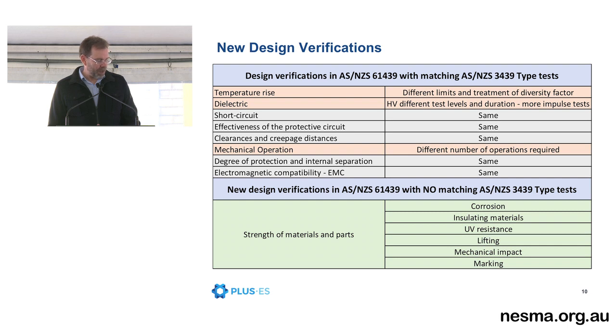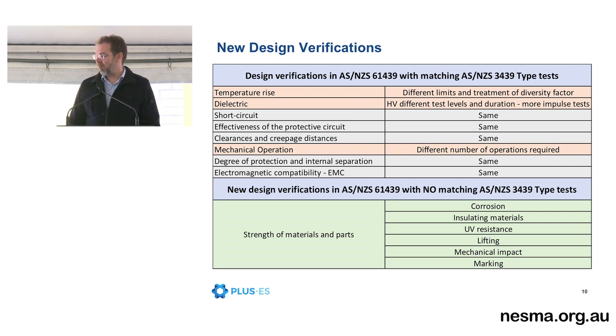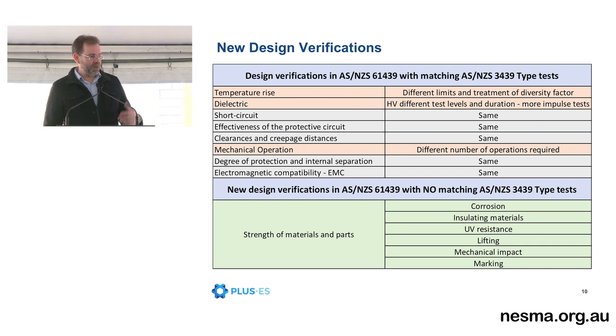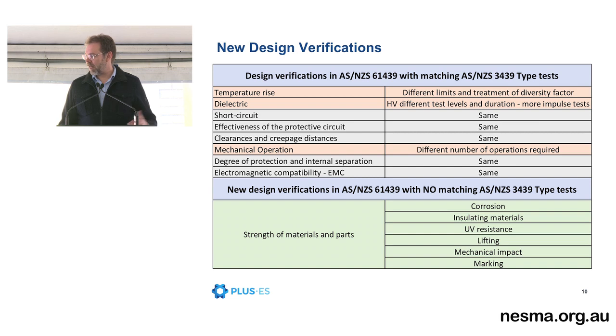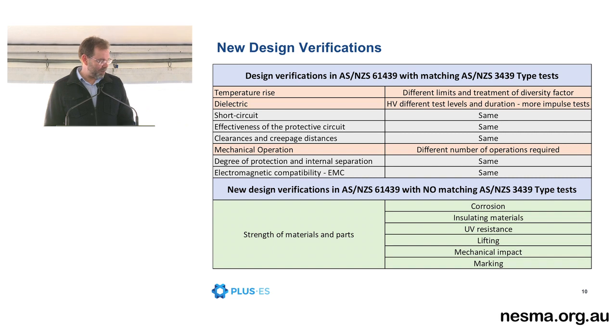The mechanical impact test. So, there's a mechanical impact scale similar to the IP scale. You know, it has a series of numbers, 1 to 10, and if you want to assign a mechanical impact rating to your switchboard, then you need to do this test. But you don't need a mechanical impact rating to be certified. So if you don't assign a rating, you don't do the test to get your certificate. So funny enough, we don't actually do that test very often either, even though we do have a range of hammers and devices to carry out those tests.